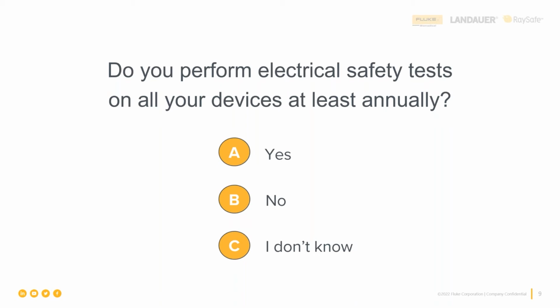When a medical device is brand new, before you put it into clinical use, you need to do the acceptance testing, and that will include electrical safety measurements. The second situation that includes incoming inspection is if you sent the medical device away from your hospital or facility for someone else to repair and it came back. When it comes back, you need to do another acceptance test, including electrical safety measurements. So acceptance testing is not included in this annual go round.